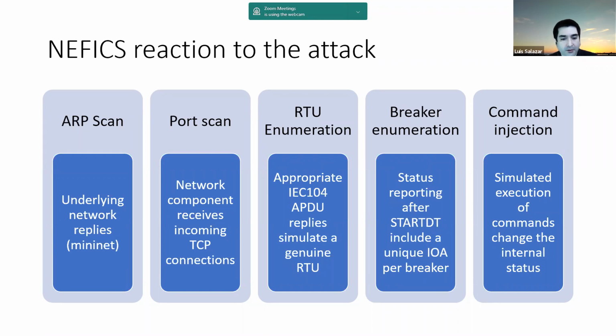As for the RTU, if you send the appropriate IEC 104 APDU, it replies accordingly. So if you send U frames, the test frames for IEC 104, it replies with the appropriate response, emulating a real RTU. For the breakers, the RTUs we made actually simulated them.